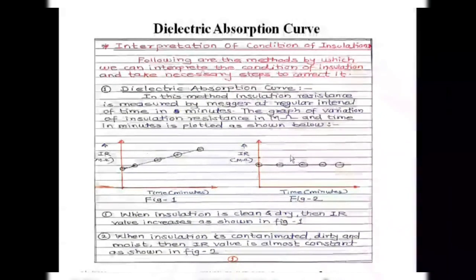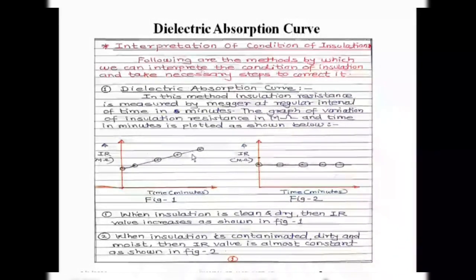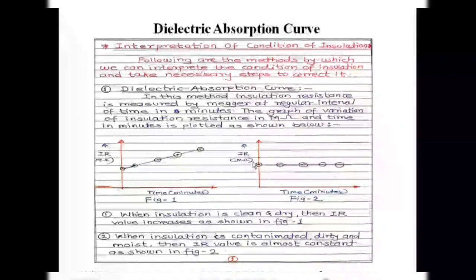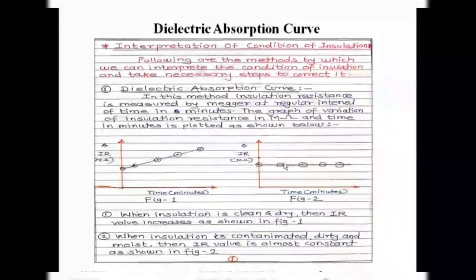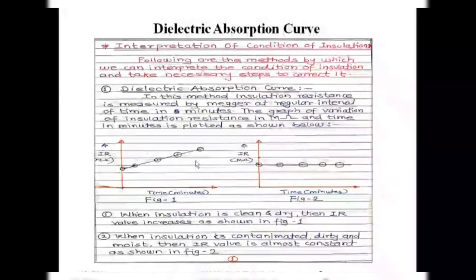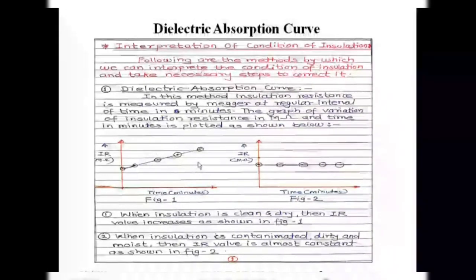By plotting the graph of insulation resistance versus time, we get the condition of insulation. The increase or constant behavior of insulation resistance is related to the dielectric absorption current flowing in the insulation. If that current flows continuously, we get graph figure number two. If the current decreases slowly and reaches zero, we get graph figure number one. This method gives us the condition of insulation by plotting IR versus time in minutes.